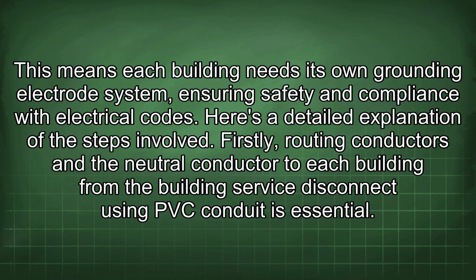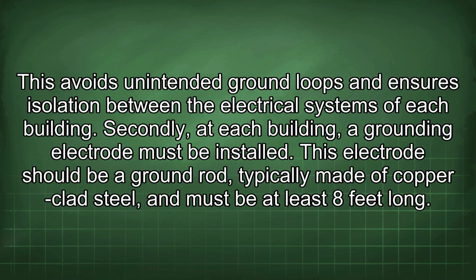Firstly, routing conductors and the neutral conductor to each building from the building service disconnect using PVC conduit is essential. This avoids unintended ground loops and ensures isolation between the electrical systems of each building. Secondly, at each building, a grounding electrode must be installed. This electrode should be a ground rod, typically made of copper-clad steel, and must be at least 8 feet long.